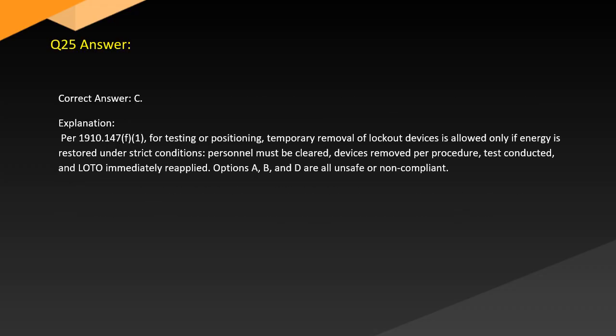Answer. Correct answer: C. Explanation. Per 1910.147 F1, for testing or positioning, temporary removal of lockout devices is allowed only if energy is restored under strict conditions. Personnel must be cleared, devices removed per procedure, test conducted, and LOTO immediately reapplied. Options A, B, and D are all unsafe or non-compliant.